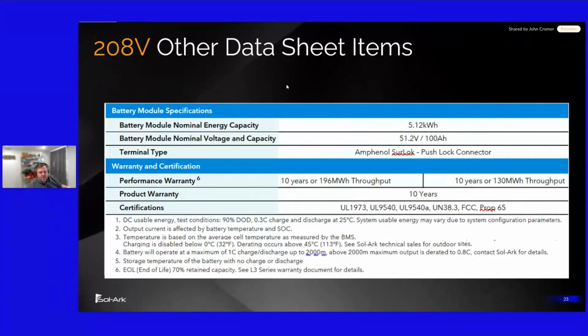We try and put very clear, accurate, and transparent information on our data sheets. So I think you'll find they have more information than what you'll find in industry. Things like being straightforward about when we say the cycle or capacity ratings, that they're called out for. When I say it's a battery with this capacity, just like a solar panel, that is at a standard test condition. So when you operate significantly outside that standard test condition, there is an amount of derating that occurs.